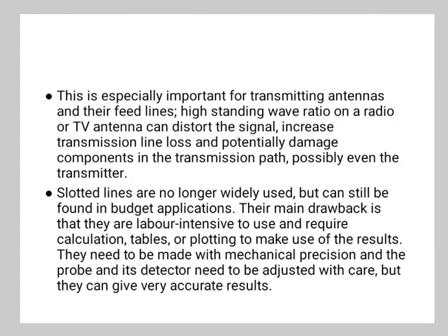The slotted line consists of a section of transmission line, that is waveguide, with a longitudinal slot approximately 1 mm wide, a probe carriage, and a vernier scale. The longitudinal slot is located at the center of the broad wall. No power is radiated by the slot for the dominant mode traveling inside the waveguide. The relative field strength of the standing wave pattern inside the waveguide is sensed by a small probe which is inserted through the slot, and this probe is located on a carriage plate that moves on the top of the waveguide.